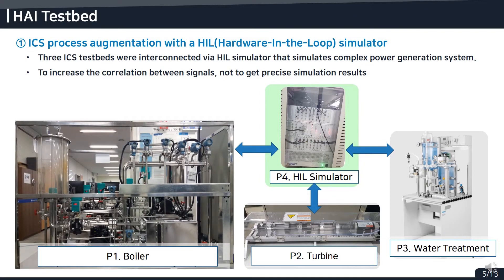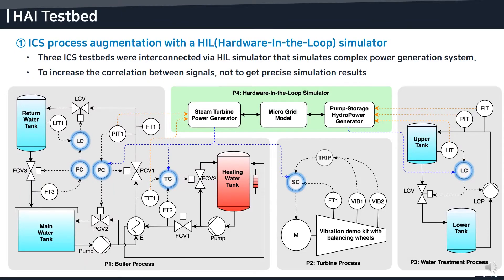Let's look at process augmentation with the hardware-in-the-loop simulator. Three real-world testbeds were interconnected by a HIL simulator. The HAI testbeds consist of six process controllers on three industrial controllers. The boiler process controlled by Emerson Ovation DCS has four controllers for water level, pressure, flow rate, and temperature. The turbine process controlled by GE Mark VIe DCS has only a speed controller. The water treatment process controlled by GE Mark VIe DCS has water level control. Finally, the HIL simulator emulates two synchronized power generators with a microgrid model. It enhances the correlation between signals, not to get precise simulation results.